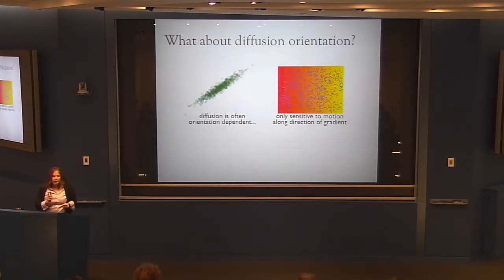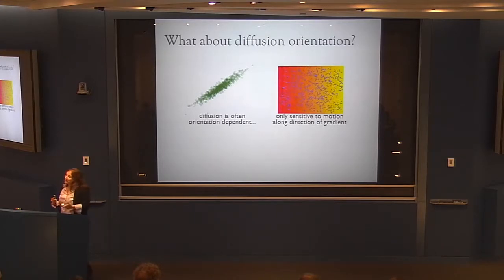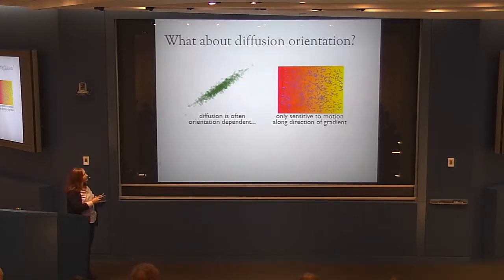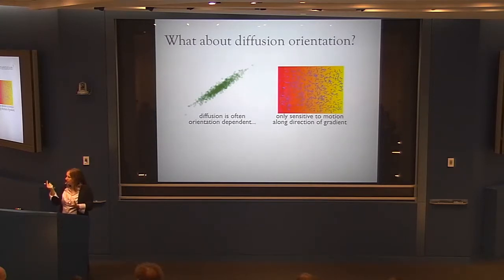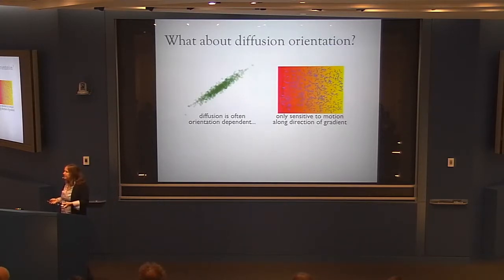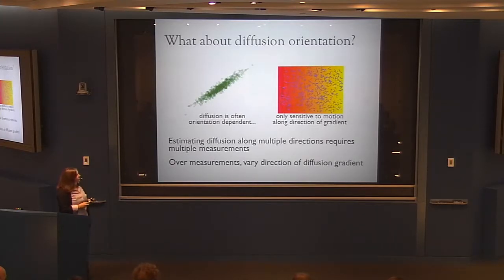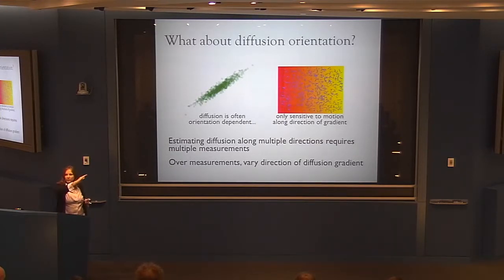What about orientation? The diffusion process is not the same in all directions. The measurement with a gradient along a given direction is only sensitive to diffusion of water molecules along that direction. If you want to estimate diffusion along different directions, you need multiple measurements with different gradient directions.